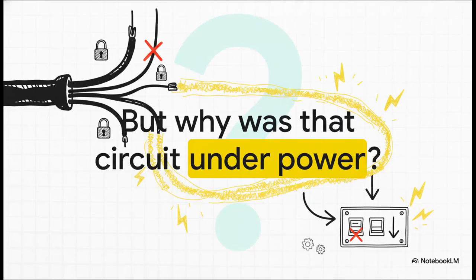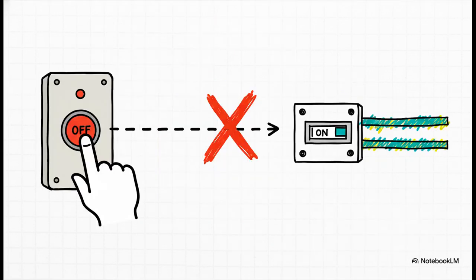And this leads us to another critical question. Okay, the technician made a mistake. But why was the opportunity for that mistake even there? According to all the procedures, that line should have been dead. Well, the investigation found something crucial. The night before the incident, the main circuit breaker back in Lelystad, the one that controlled this line, failed to respond to a remote off command. And the report is crystal clear on this. The established procedures say that in a situation like that, the circuit should have been manually de-energized and taken out of service. But it wasn't. This was the pre-existing condition that set the whole stage for disaster.